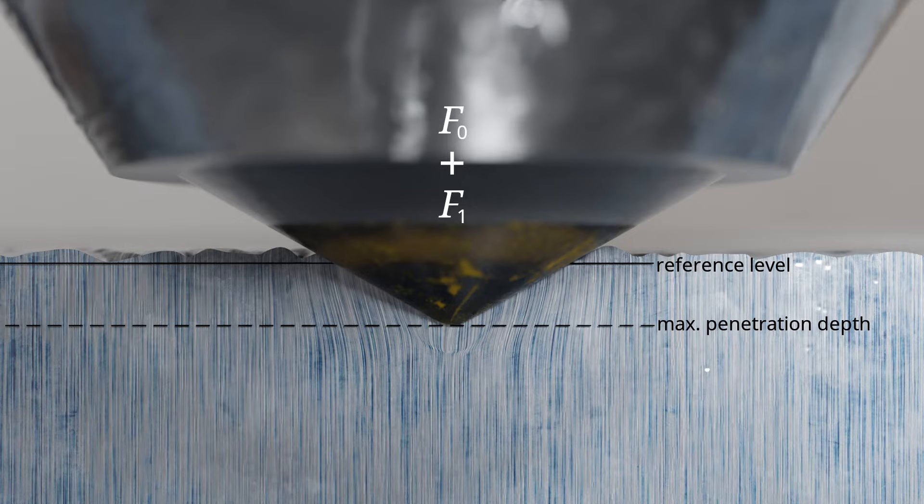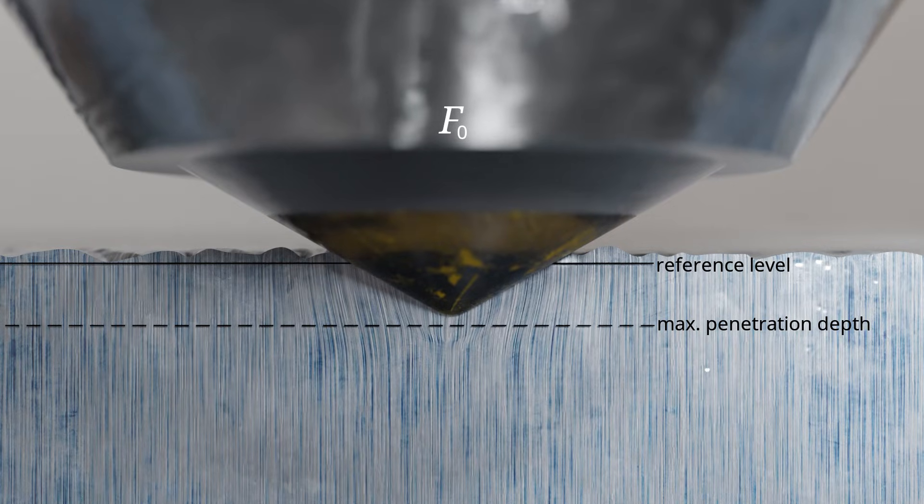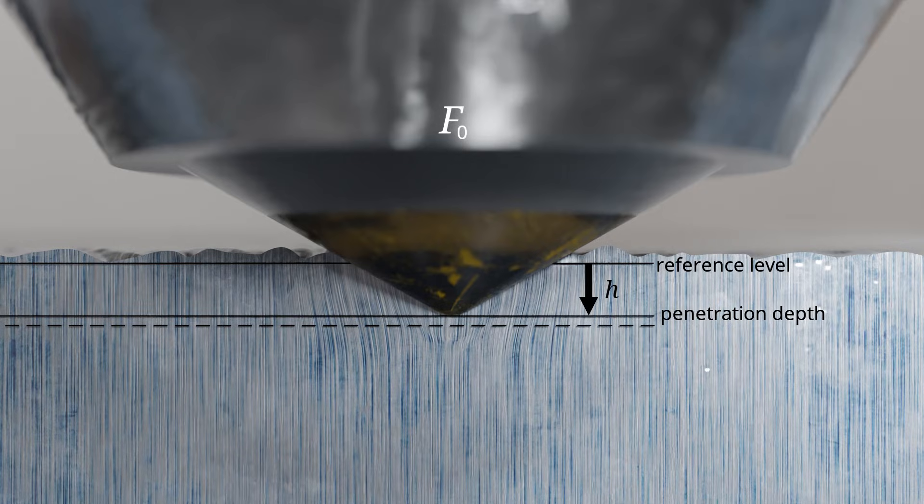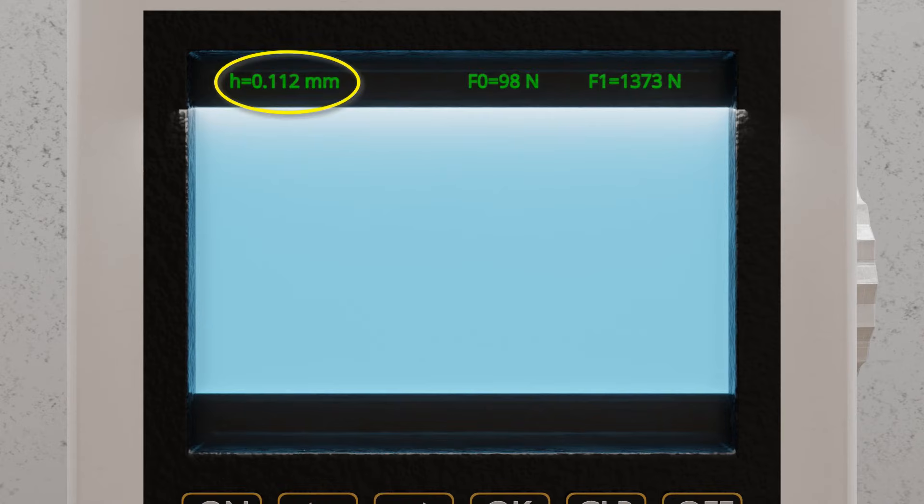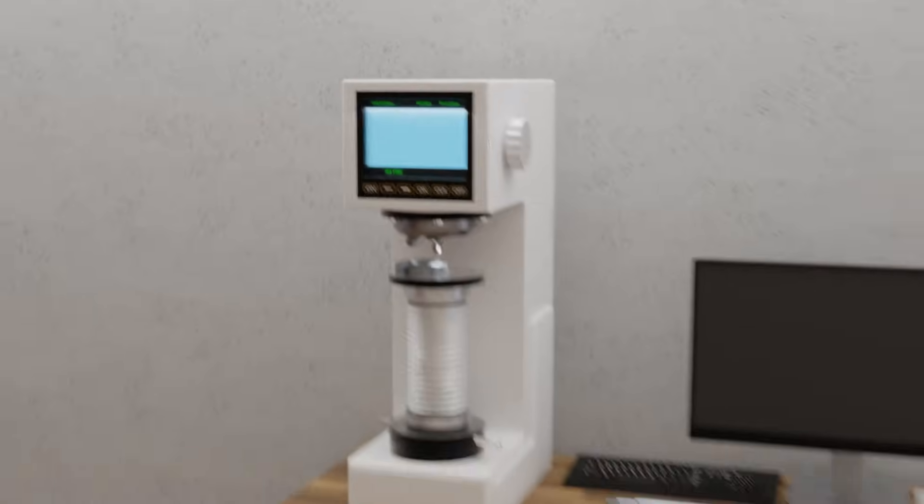After the indenter penetrates the material surface with the applied total force, the test force F1 is removed. The material is then subjected only to the preload F0, causing the indenter to lift slightly due to the elastic deformation of the sample. However, contact with the sample is maintained. The remaining indentation depth H, measured while maintaining the preload F0, is used as the basis for calculating the hardness value. In this example, an indentation depth of 0.112 mm is achieved using the diamond cone. This corresponds to a Rockwell hardness value of 44 HRC. The fundamental steps for calculating this hardness value from the measured penetration depth will be explained in more detail in the following.